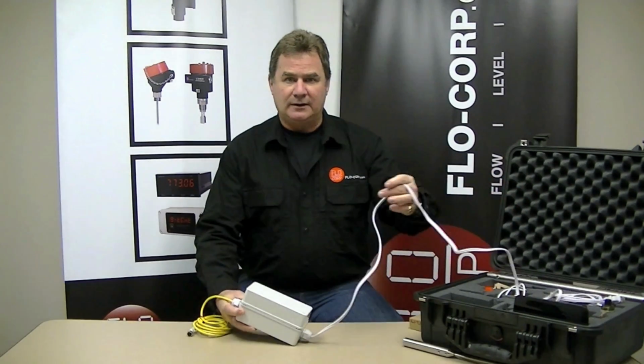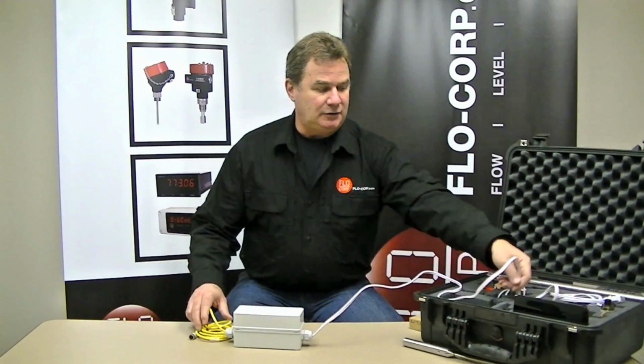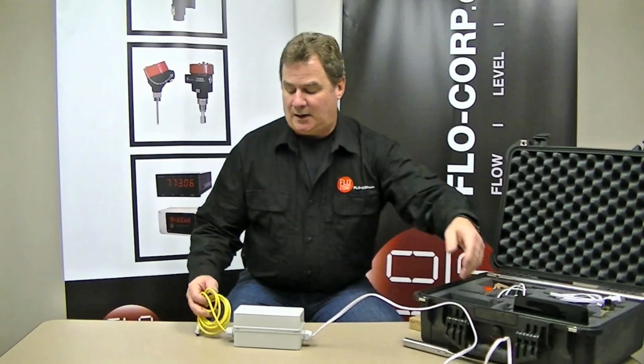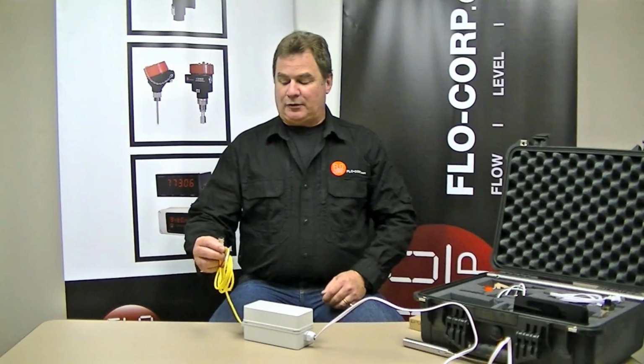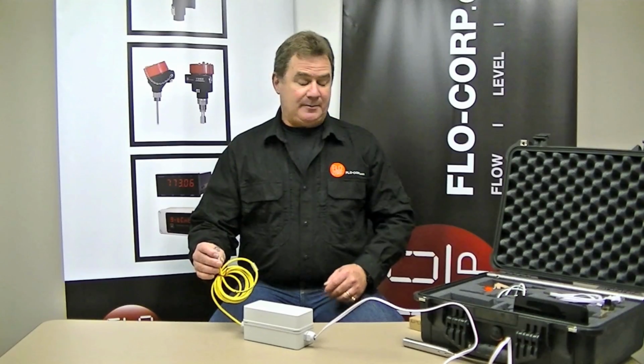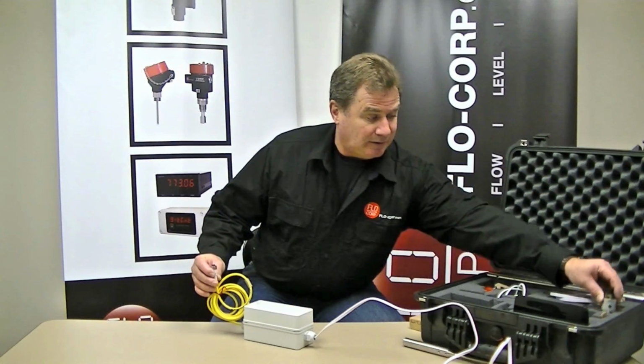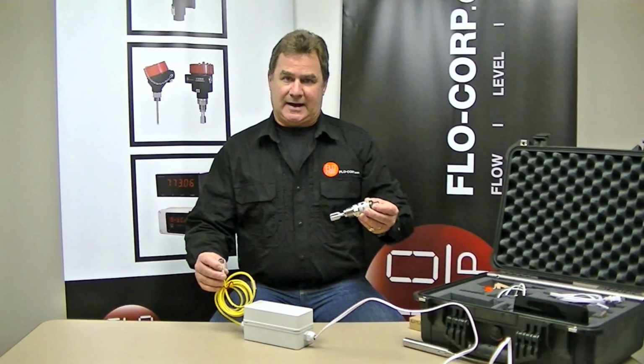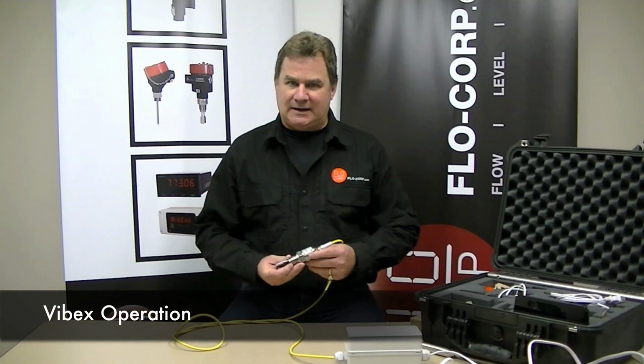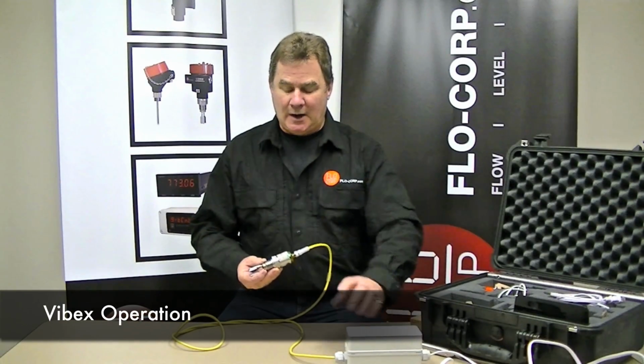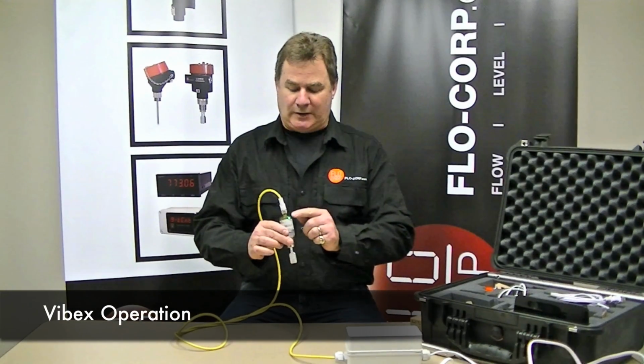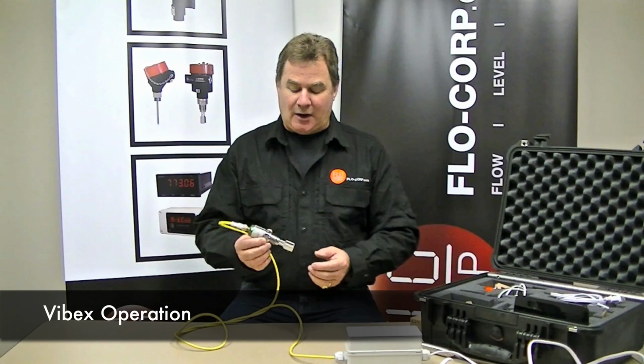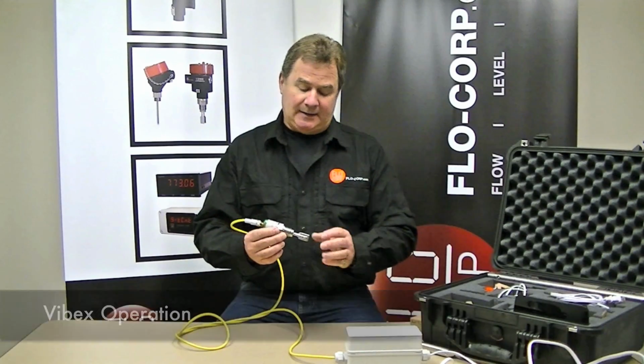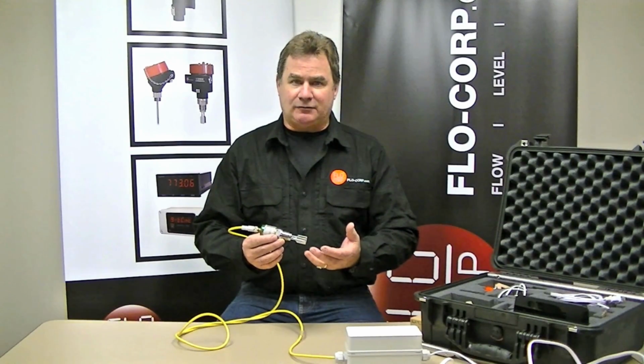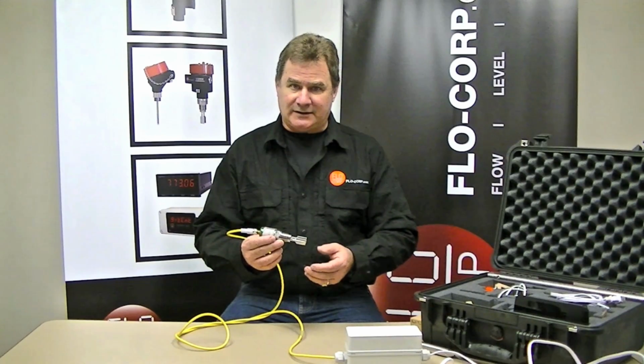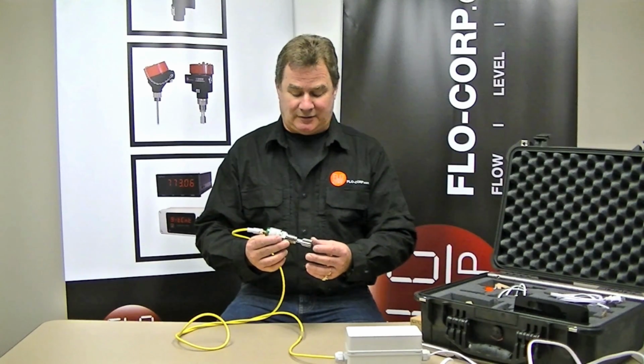There is a power cord that will need to be plugged in to line power, and there's also a yellow cable that will need to be connected to the Vibex, which sits just above the controller on the lower right hand side. Once you have the Vibex connected to your power source, you'll notice that the Vibex has a green light that's lit, and also that you can hear the Vibex operate at its resonant frequency at 1200 Hertz. That's the high-pitched vibration sound you hear.